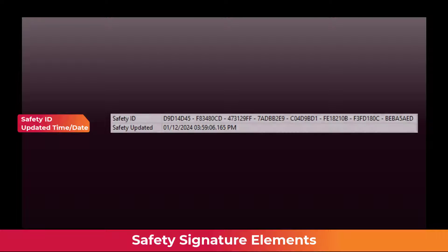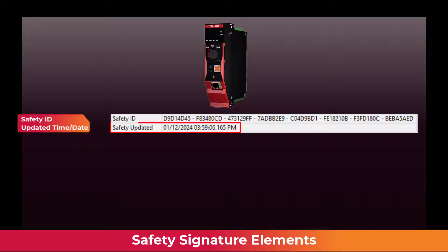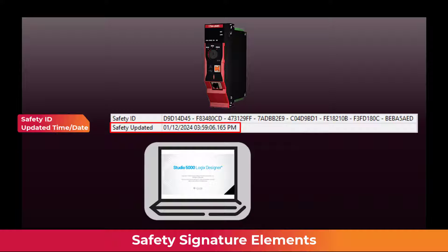The ID is generated by the GuardLogix controller and is the primary indication of safety integrity. The timestamp is generated by Logix Designer software and provides an indication of when changes were made, based on the PC time when the safety signature was generated.